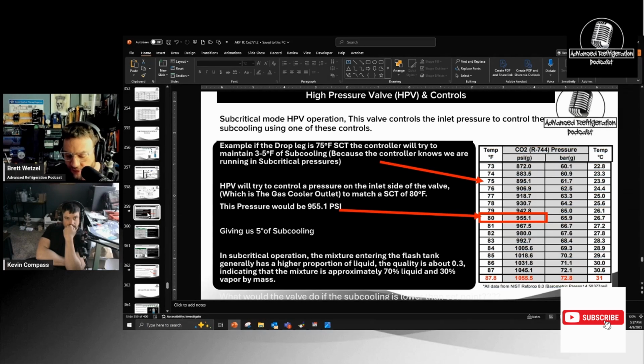I was like, hey, think about it, right? If the unit is running subcritically and trying to maintain subcooling, it's going to try to close down that HPV as much as humanly possible to achieve that subcooling. But it's going to close it down so much that it's going to end up going off on high pressure.